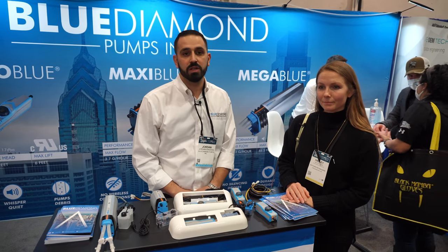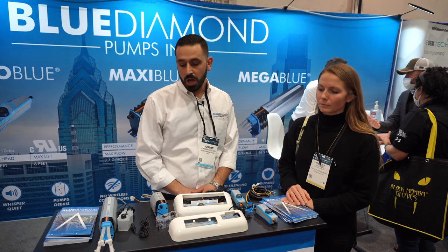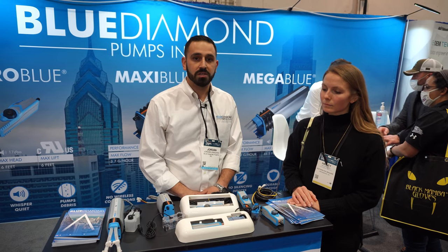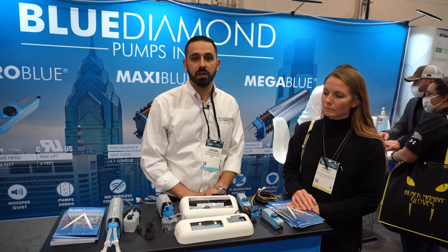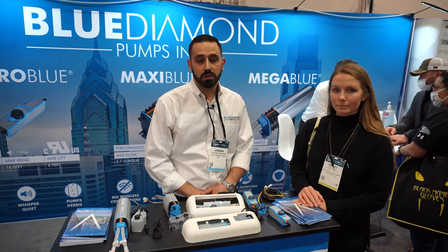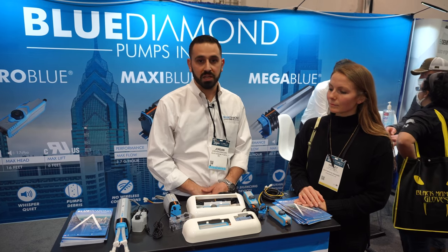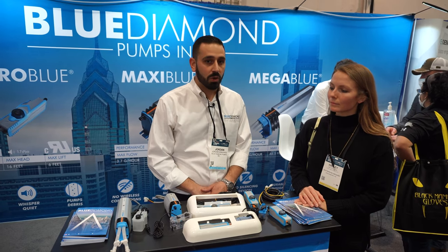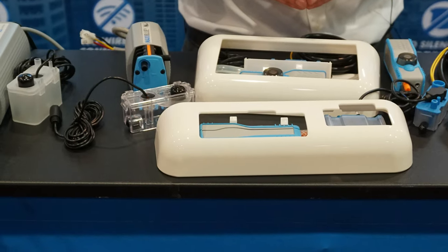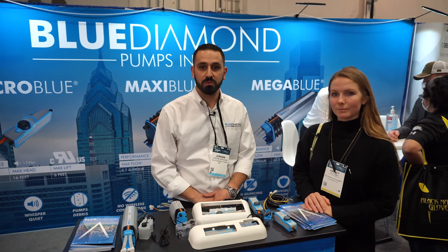What makes Blue Diamond different is our rotary technology. We operate similar to a scroll compressor. The pumps are actually creating a true mechanically driven suction, pulling the condensate into the pump and forcing it to the outlet under pressure. So it gives you a very versatile product — something that can be installed above your unit if necessary, and can be installed in any orientation. It doesn't require filtration because the pumps can tolerate debris. Fundamentally, that's what makes Blue Diamond different: the rotary technology and where all of the advantages stem from.